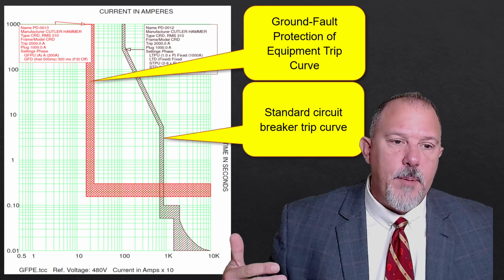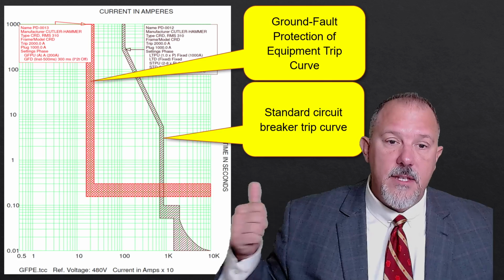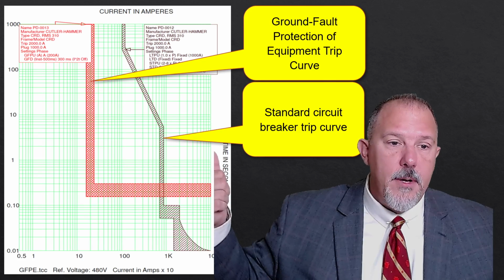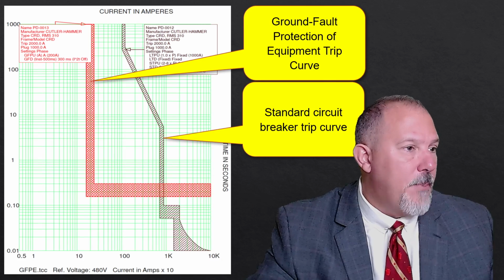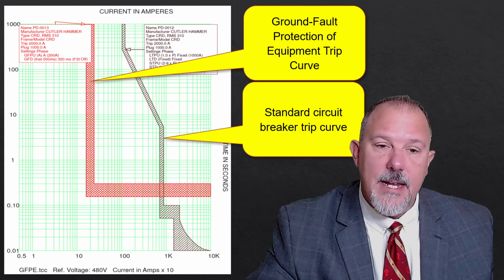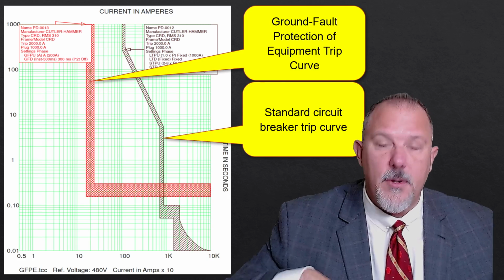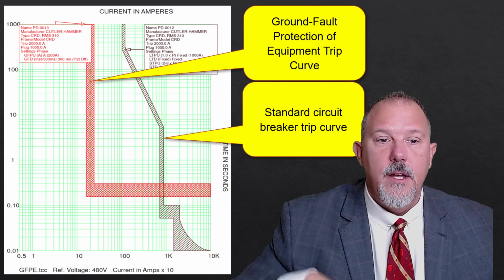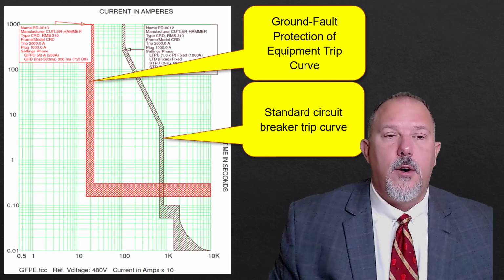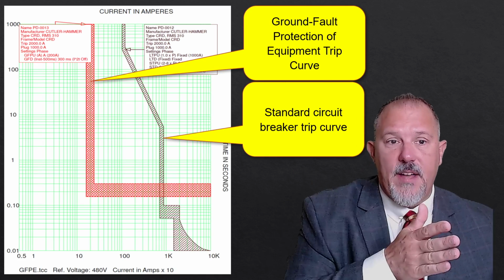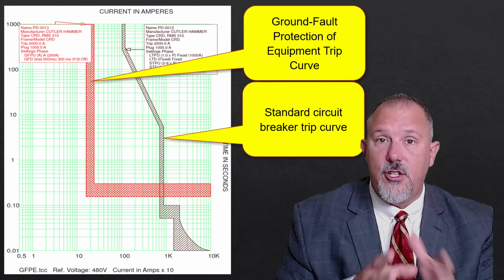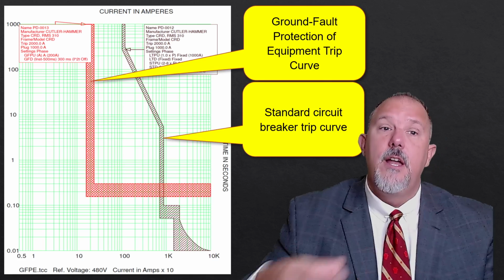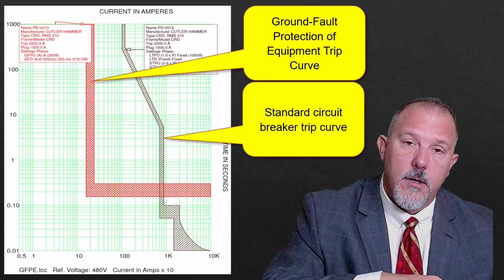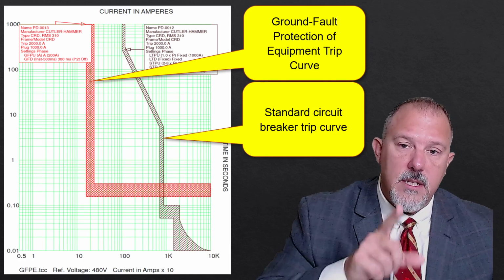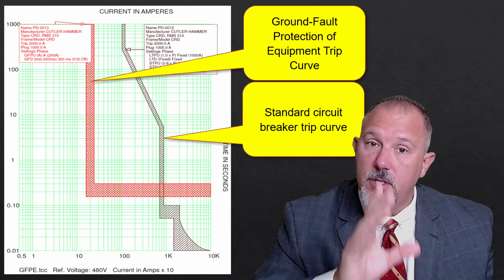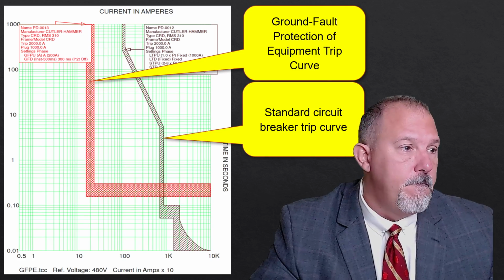When I add GFPE now, I'm permitted to take this curve, this red curve, up to 1 second. I'm permitted by the code to take that to a 1 second clearing time based upon 230.95. This is lower and the pickup value is lower. So this is trying to address those arcing currents that are going to occur below the instantaneous pickup of that breaker. And remember, this went in in 1971.